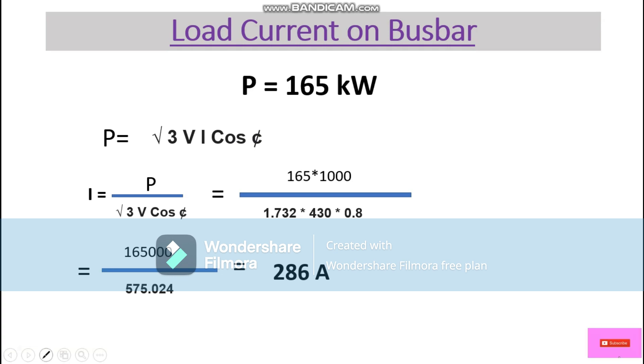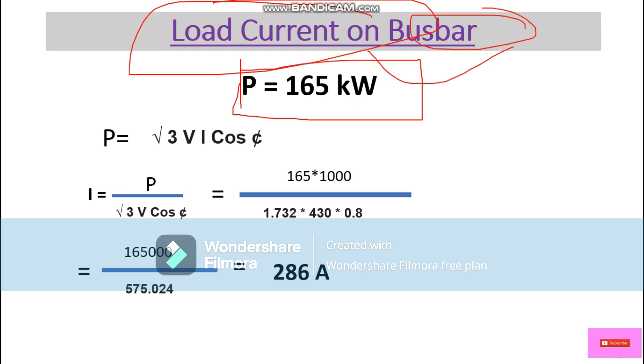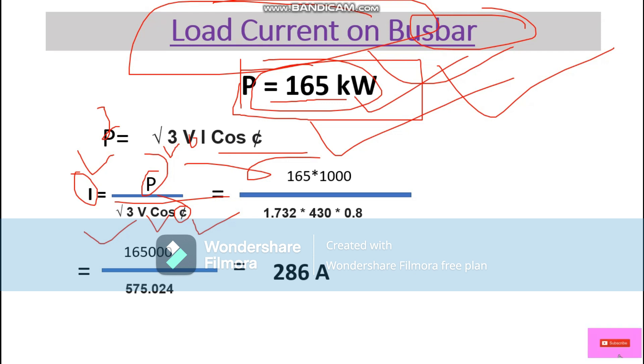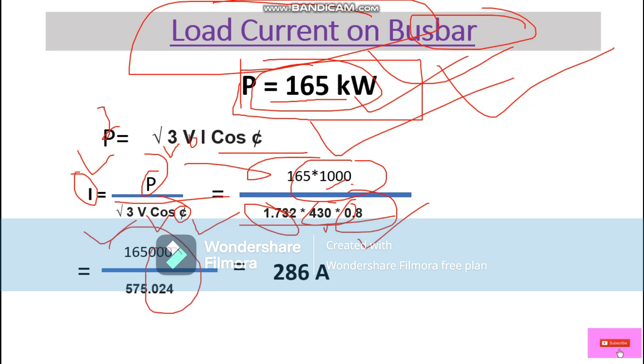Based on the connected load, we now calculate the load current. For three-phase power: P = √3 × V × I × cos φ. Rearranging for current: I = P / (√3 × V × cos φ). Substituting values: P = 165 kW (165,000 W), √3 = 1.732, phase voltage = 430 V, and power factor = 0.8. The calculated current comes out to 286 amperes, which is the load current on the bus bar.